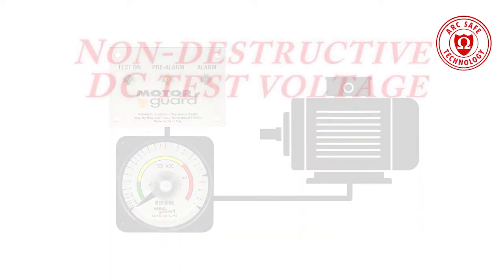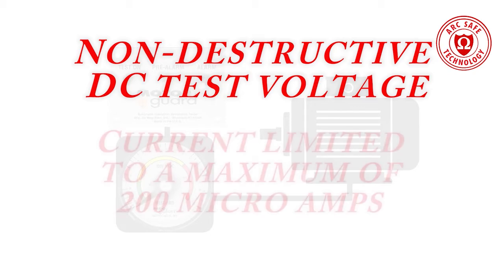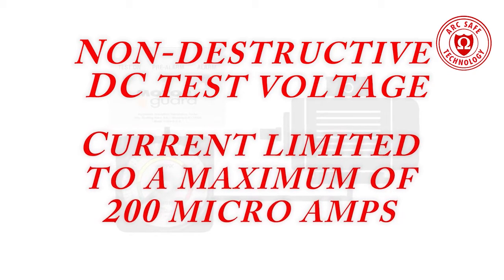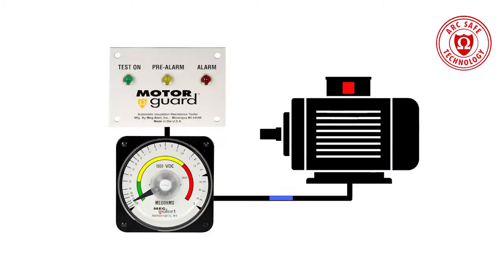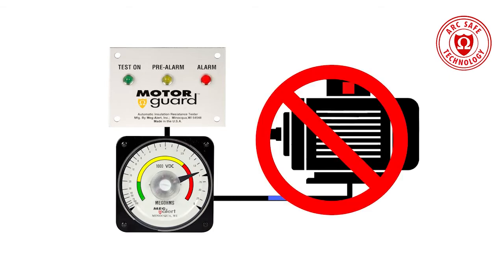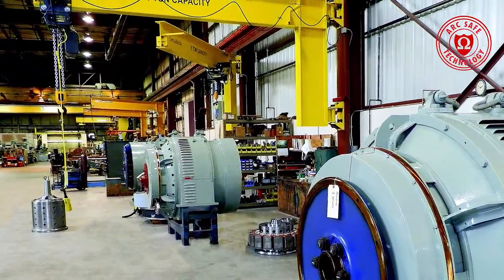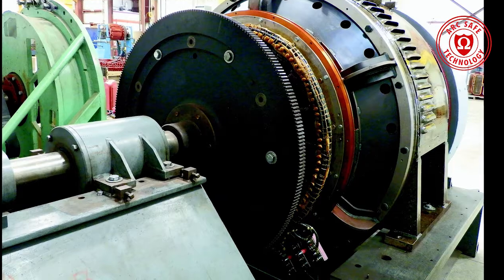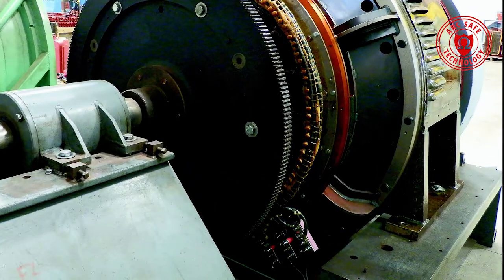MegAlert uses a non-destructive DC test voltage, current limited to a maximum of 200 microamps, to continually test the insulation resistance of your equipment when it is offline, and then offers a pre-alarm warning if it senses insulation degradation. If the MegAlert unit identifies an imminent, critical failure, it locks out the equipment, keeping your workers and equipment safe, and notifies the appropriate authorities in any one of several different methods. MegAlert allows the appropriate personnel to correct the condition prior to anyone being placed in harm's way.